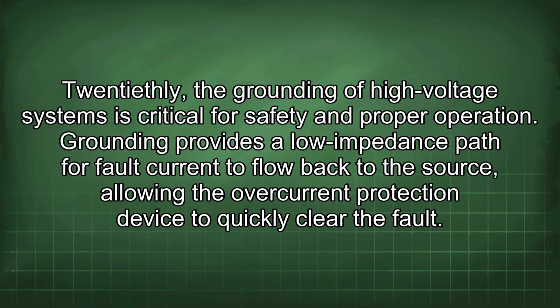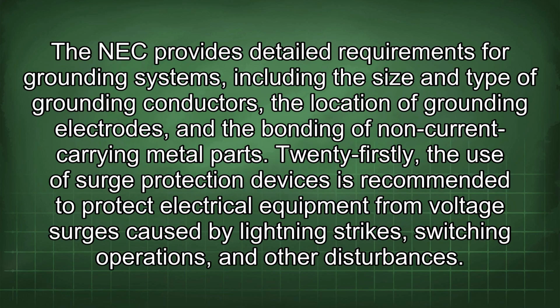20thly, the grounding of high-voltage systems is critical for safety and proper operation. Grounding provides a low-impedance path for fault current to flow back to the source, allowing the overcurrent protection device to quickly clear the fault. The NEC provides detailed requirements for grounding systems, including the size and type of grounding conductors, the location of grounding electrodes, and the bonding of non-current carrying metal parts.